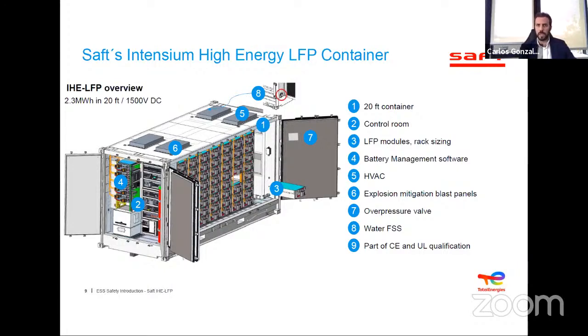Then we have the blast panels, number 6, which mechanically open in case of a rapid increase of pressure, avoiding rupture of the container and directing gases and flames to the top part of the container. This protects people nearby, but at the same time avoids directing pressure, gases, heat, and flames toward equipment nearby. So we accept the loss of the container, but protect the equipment nearby.